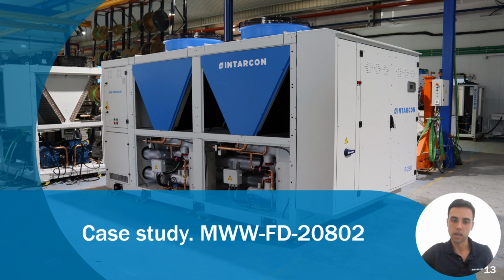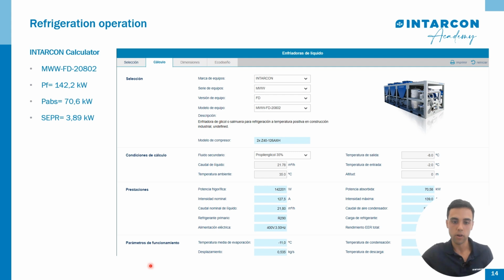Now let's see the case study of a MWW-FD-20802 full inverter propane system that is for medium temperature with chassis 2, and it counts with two compressors of 40 horsepower. The INTARCON calculator offers a cooling capacity of 140 kilowatts and electrical power consumption of 70 kilowatts, and also a SEPR of 3.89. For the use of a propylene glycol 35%, we have got a glycol flow of 21.88 cubic meters per hour.